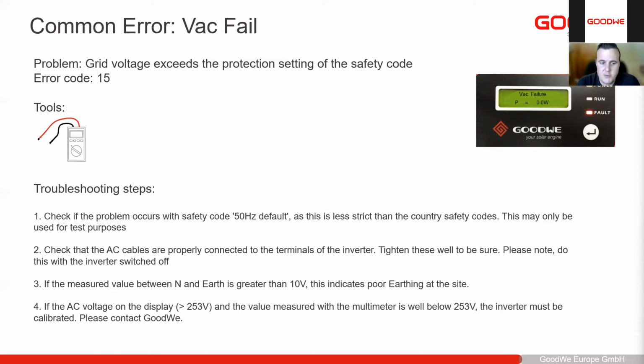Measure between neutral and earth to see if the voltage is less than 10 volts. If it's greater than 10 volts, then our grounding is poor. And if the AC voltage on the display is greater than 253 volts, and you measure with the multimeter that is well below your country regulation, then the inverter might need to be calibrated or replaced. Then you can just contact us for that.